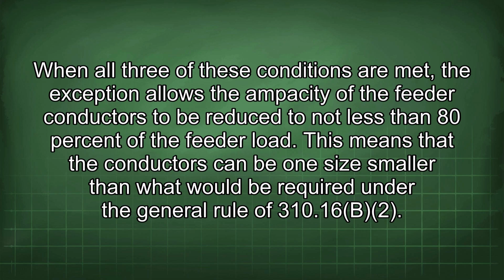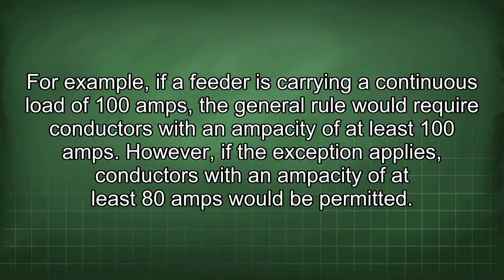This means that the conductors can be one size smaller than what would be required under the general rule of 310.16b2. For example, if a feeder is carrying a continuous load of 100 amps, the general rule would require conductors with an ampacity of at least 100 amps. However, if the exception applies, conductors with an ampacity of at least 80 amps would be permitted.